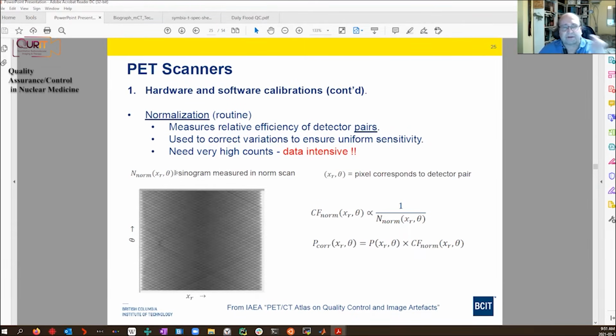Again, it can vary with the technology. I'm just giving a basic overview of it. What you want to do is measure very high count sinograms that you're going to be using to correct the clinical sinograms. And so here is a normalization sinogram. You see some sort of systematic variations. Just to remind you, each pixel in a sinogram corresponds to a detector pair, but it also corresponds to the angle and the radial position of a line of response. And so this is measured.